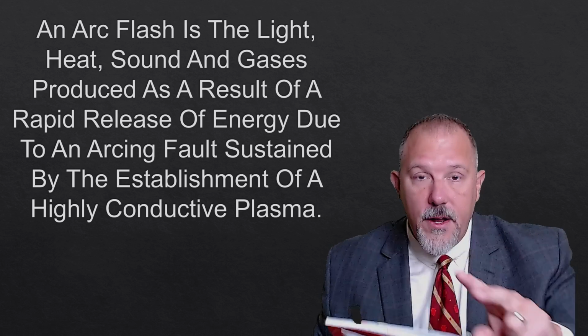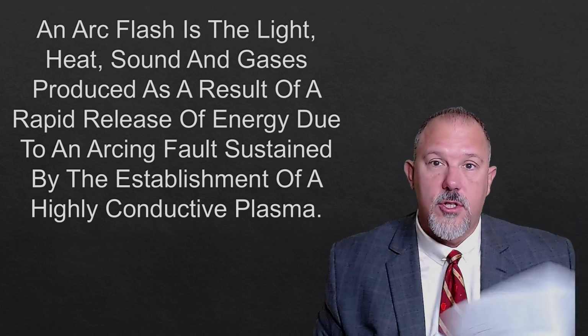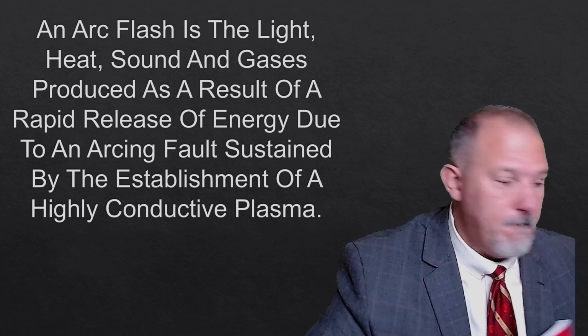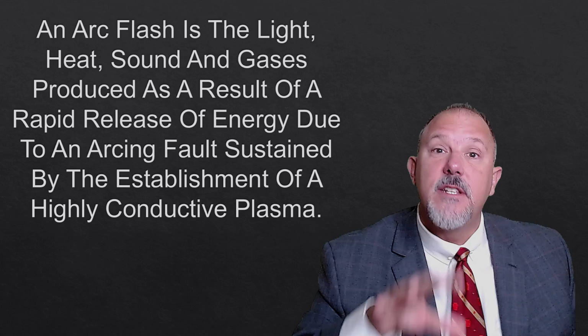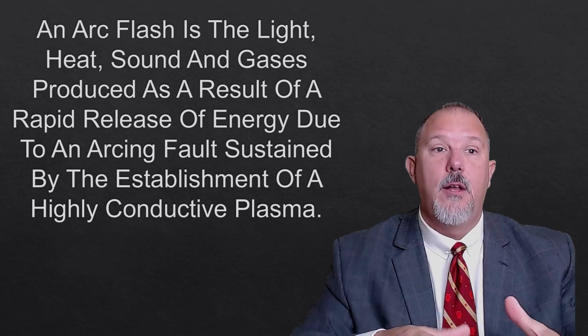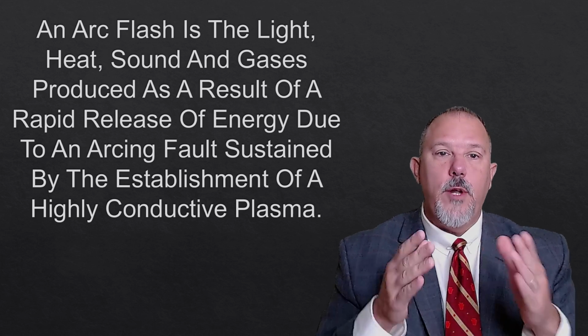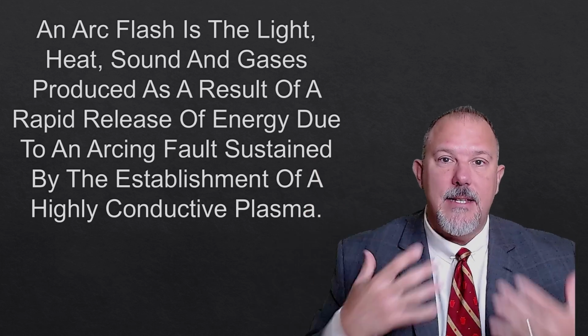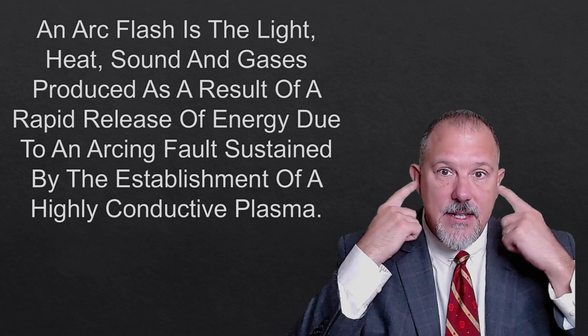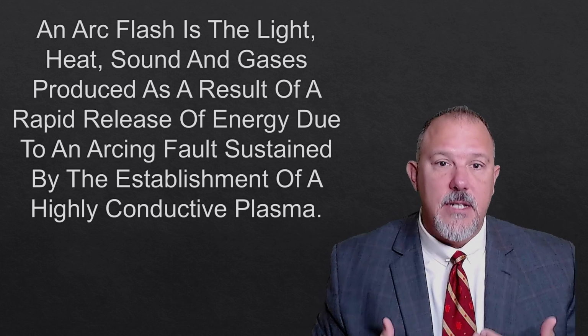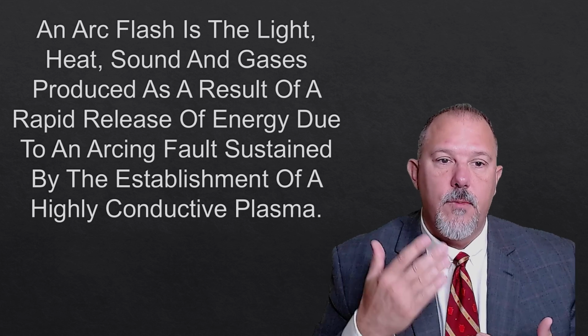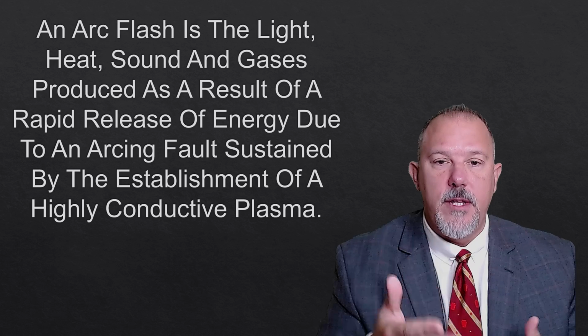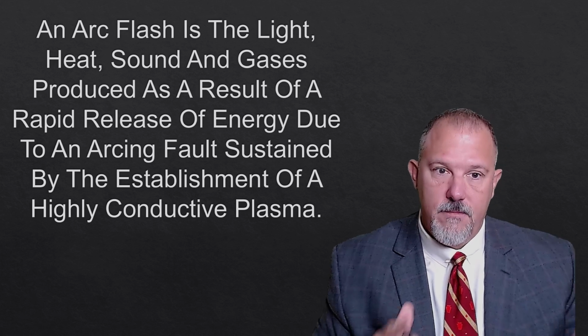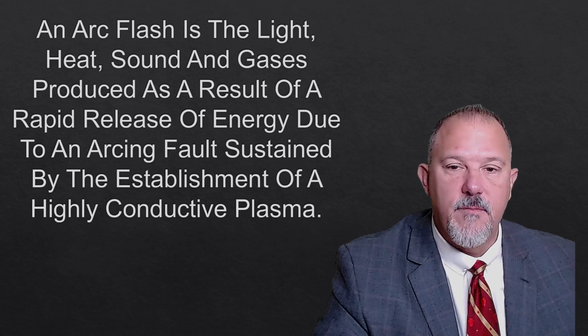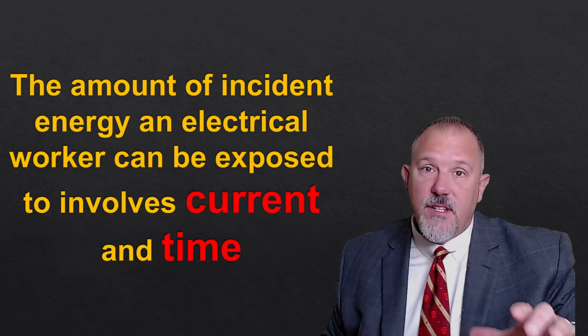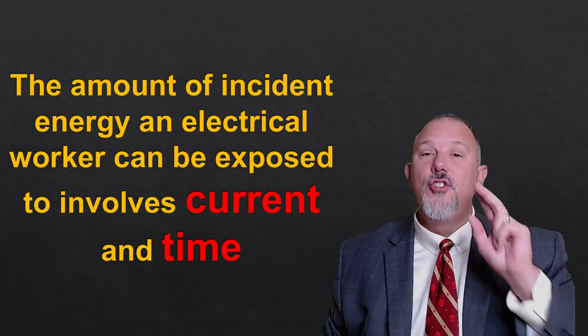The two very important key words that are associated with risk. Now, what we're talking about right now is the severity. So we're talking about what is the severity of an arc flash event. We know we have light, eyes, heat, skin, sound and gases, taking in gases into your lungs, as a result of a rapid release of energy due to an arcing fault, sustained by the establishment of a highly conductive plasma. Now, the amount of incident energy is dependent upon two critical factors.